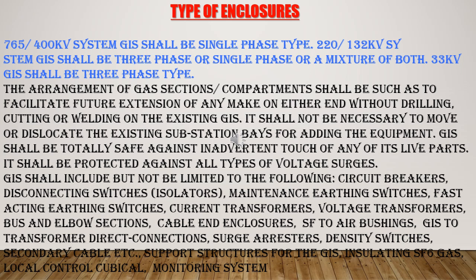For 765-400 kV system, GIS shall be single-phase type. For 220-132 kV system, GIS shall be three-phase or single-phase or a mixture of both. 33 kV GIS shall be three-phase type.